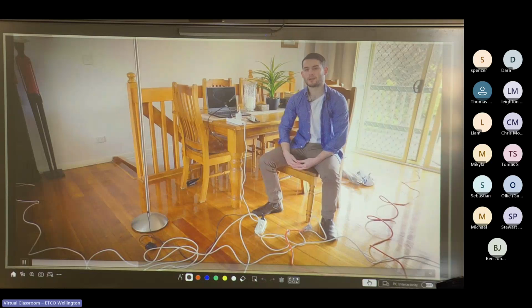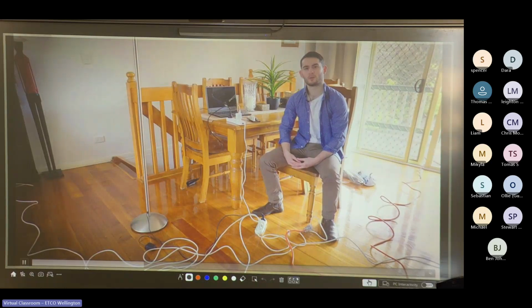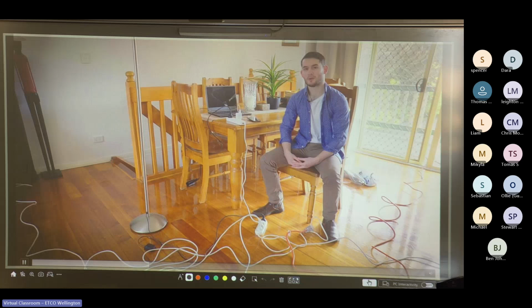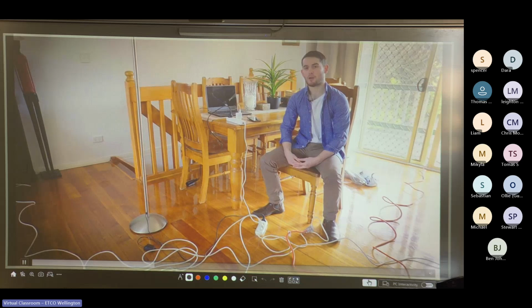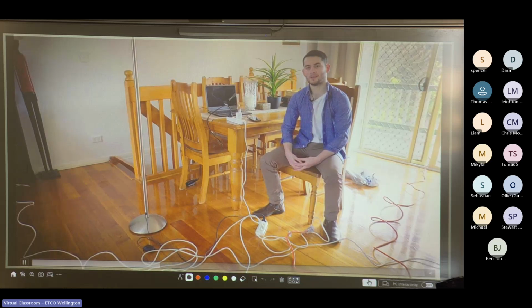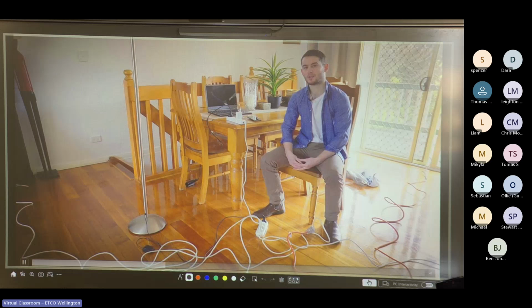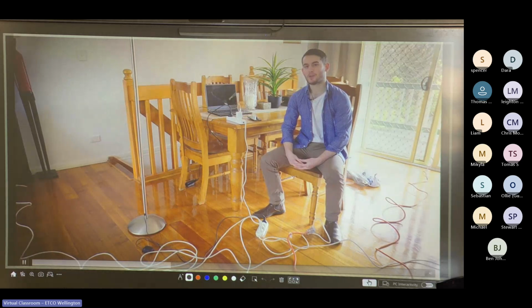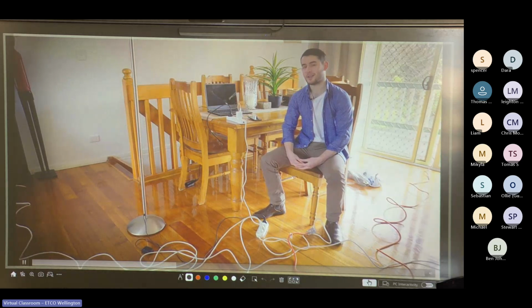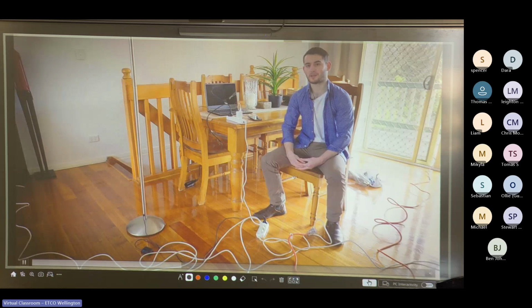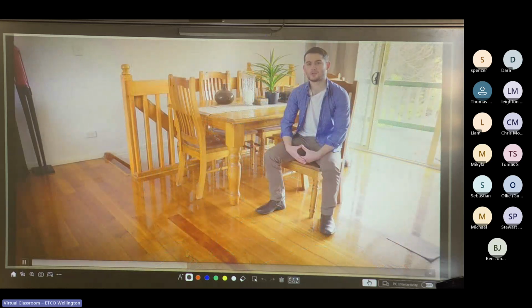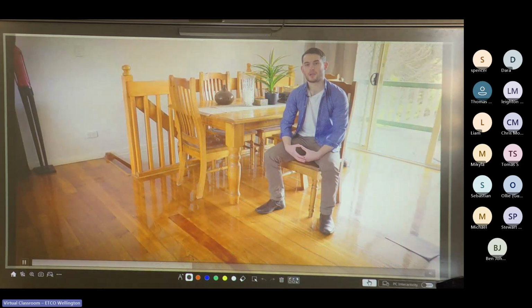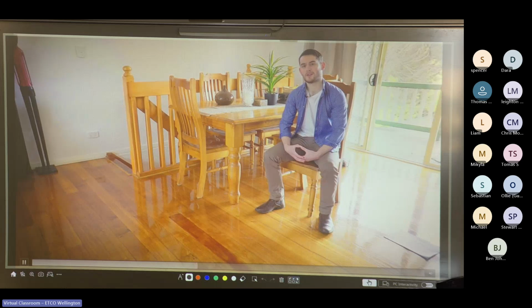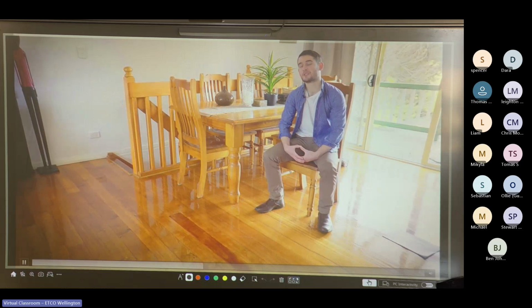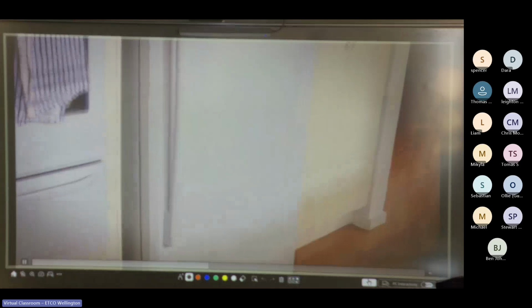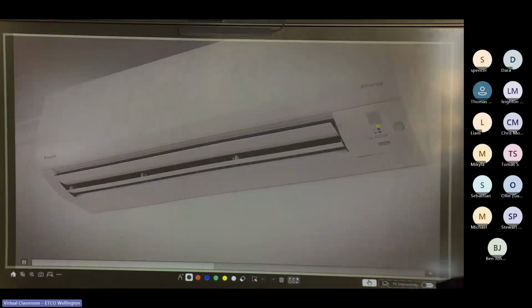Why would you use a manual transfer switch? Well, without one, if you've got a generator, you can always run an extension cord into the house and power portable lights, appliances, power boards and extension cords. But things quickly become complicated and potentially dangerous with things lying around all over the place. But when you add a manual transfer switch, all you have to do is plug the generator into a single outlet outside the house. Then you'll have fixed lighting, power outlets, and all your appliances as normal, including hot water units and air conditioners.